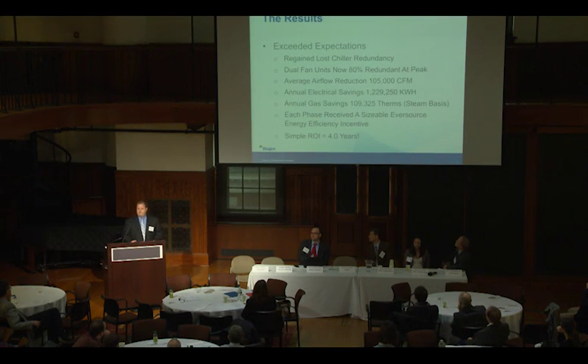It really exceeded what we expected to get out of it. We gained back chiller redundancy, and a lot of redundancy in our fans, so now we can take a fan down and have more than an hour to do maintenance. The average airflow reduction was pretty impressive — 100,000 CFM right off the top — and then you can go through the KWH and therms, the therms basis converting to steam via our CHP on site.